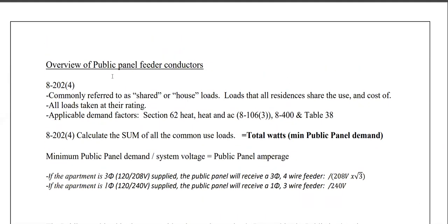Public panel feeder conductors are slightly different. The only rule that is utilized here is 8202 subrule 4. Now, this is commonly referred to as a shared or house load that all residences share the use and cost of. All loads are taken at their rating, and applicable demand factors.